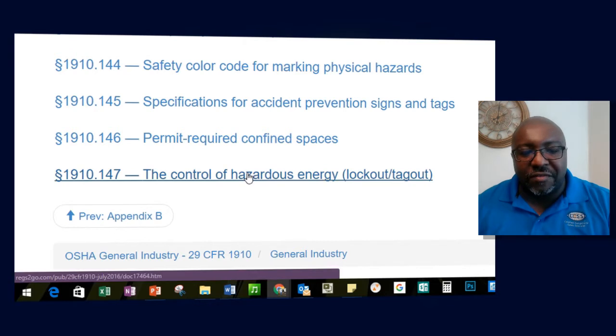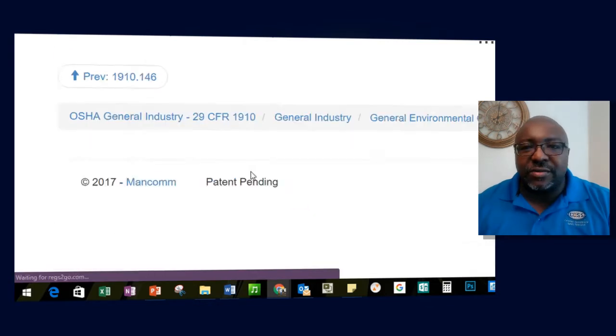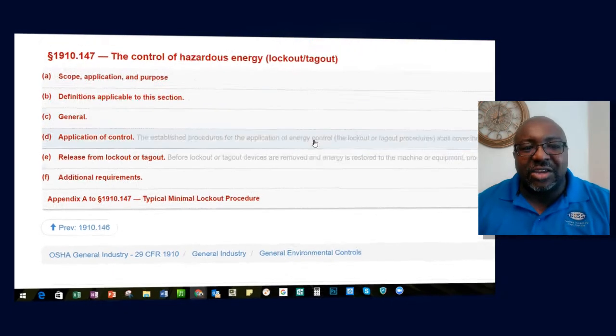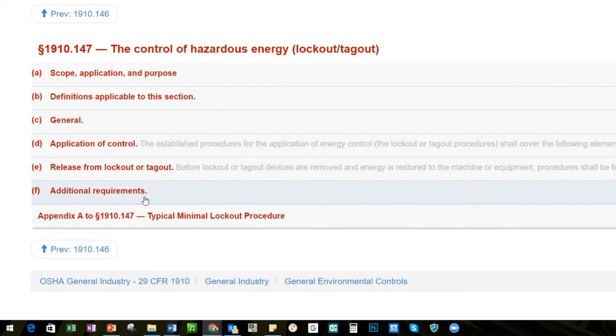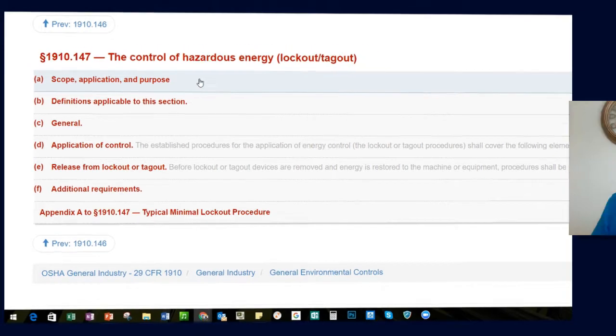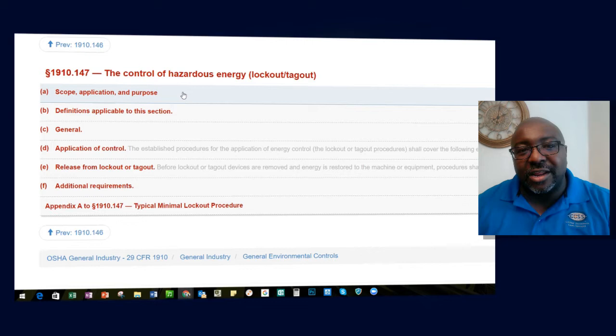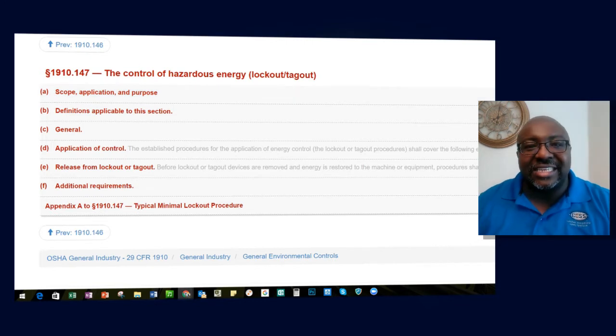There is control of hazardous energy, lockout tagout, which is in section 147. In that section, the scope, the applicability, the general controls, releasing the lockouts, having a program - pretty much all of this is being violated if they are actually regulated under OSHA. And since this was a county facility in Florida, they are exempt from OSHA. So the private sector counterpart would have a violation of 1910 section 147. So I'm going to highlight that.